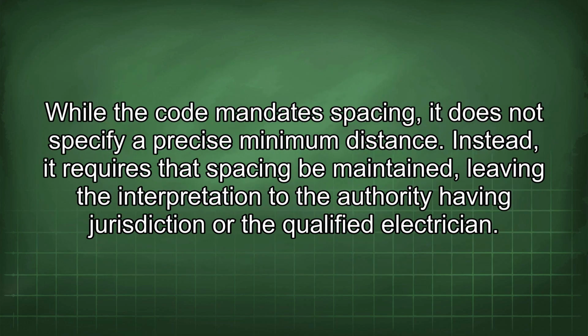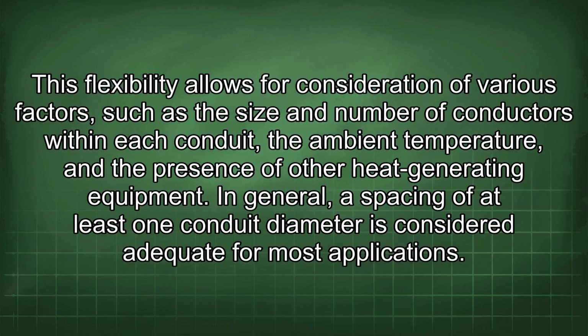While the code mandates spacing, it does not specify a precise minimum distance. Instead, it requires that spacing be maintained, leaving the interpretation to the authority having jurisdiction or the qualified electrician. This flexibility allows for consideration of various factors, such as the size and number of conductors within each conduit, the ambient temperature, and the presence of other heat-generating equipment.